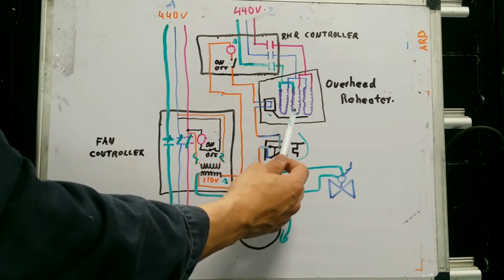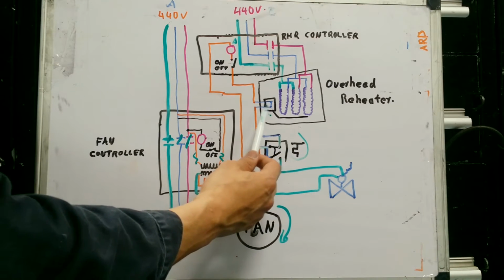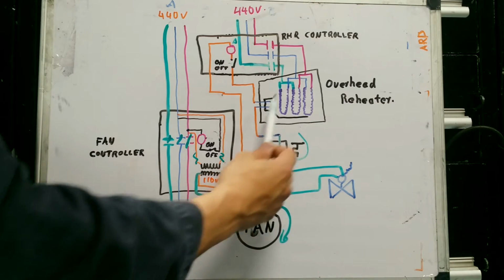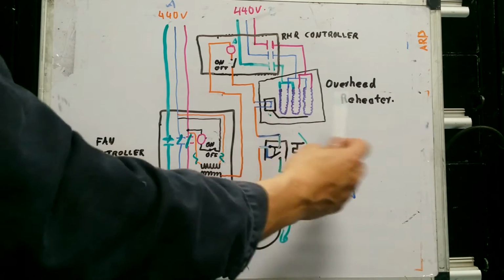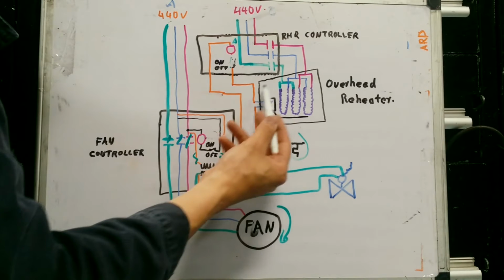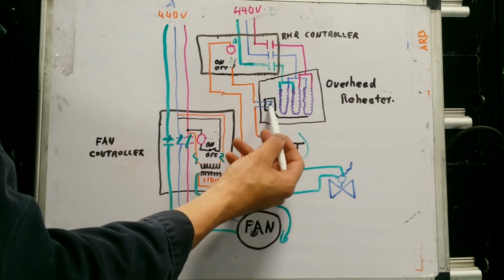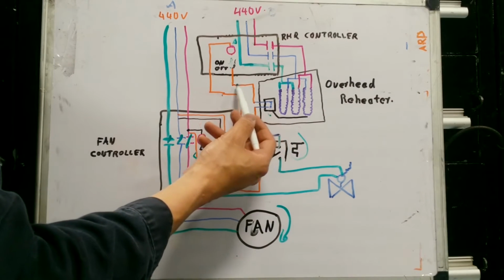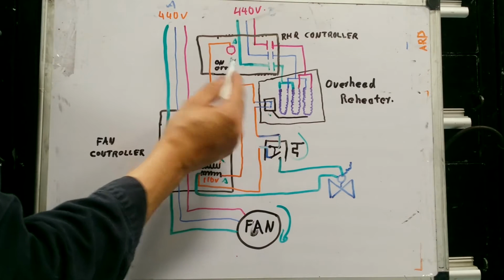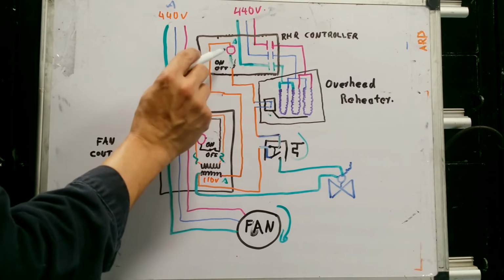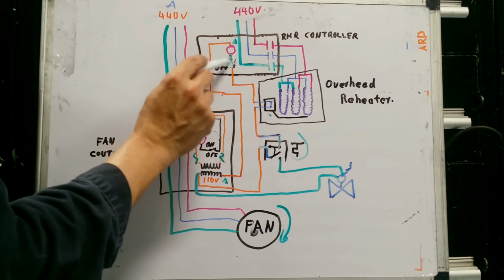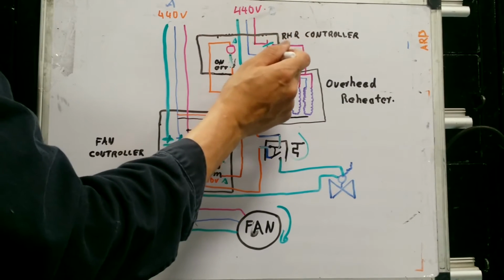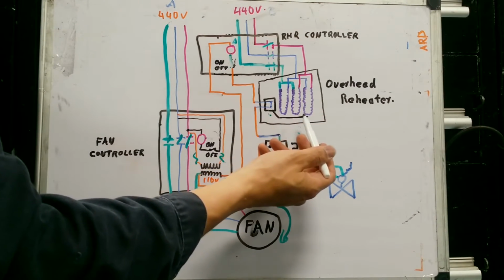If in case it gets too hot over here, this will open. But assuming that this is not too hot, because air is flowing through it, and assuming that there is not an overtemp condition over here, this switch will be closed and power will continue and you get to here. And as you have this on and off switch closed, boom, you put power into this coil, and that means that this contact's closed and therefore the heaters come on.